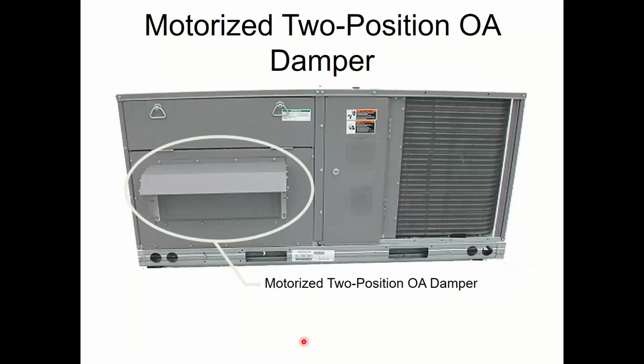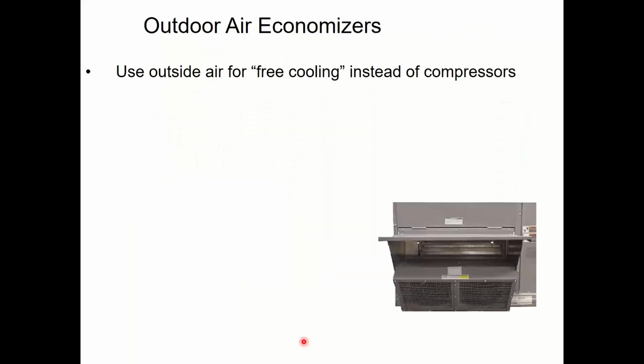You can do this with just a regular manually positioned damper. You can do it with a motorized 2-position damper like I'm showing here, or you can do it with an economizer. You're probably going to do it with an economizer. Mike asked a question, what % of commercial buildings have OA dampers that do not close when unoccupied? I don't have any statistical data, but it's well over 90% in my observation, looking at a few thousand buildings over the past 20-some years. It is very, very rare to find a building that has dampers that shut during the unoccupied mode.